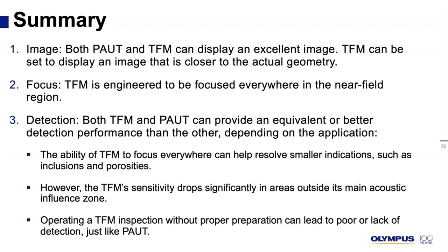When using phased array in focus mode, combined with a good quality probe and good quality wedge, the results can be as good as TFM. But this only applies in the area where the beam is focused.